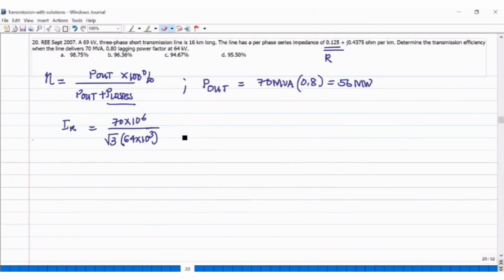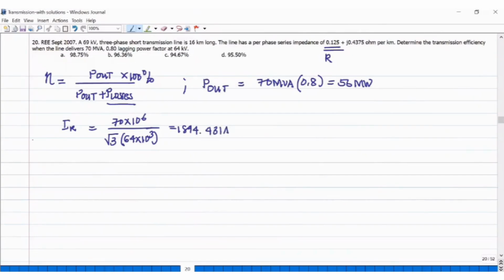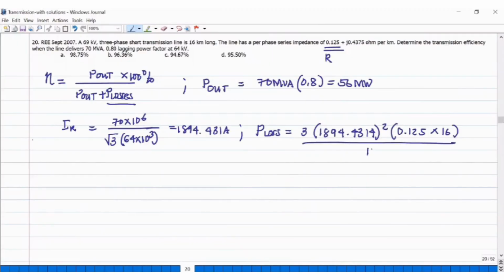70 exponent 6 divided by square root of 3 divided by 64 exponent 3 is 1894.431. So the total power loss is 3 times 1894.4314 squared times the total resistance 0.125. Naka-ohm per kilometer pa yan, kaya times 16 kilometers. Then divided by 1 million.